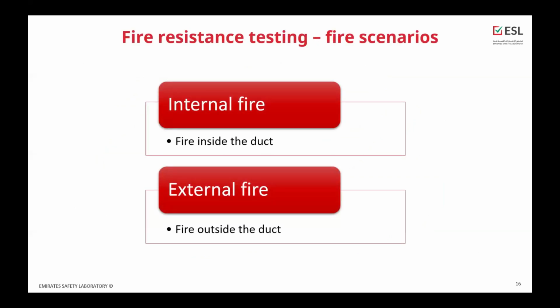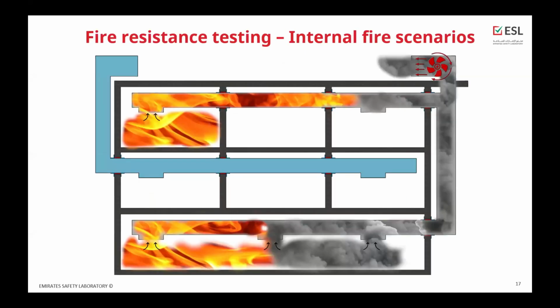During the test, we are doing fire resistance testing of the ducts under two scenarios: internal fire and external fire. Internal fire simulates the situation where the fire is pulled into the duct system. However, as you can see on this graph, the duct is also exposed from outside, so we have both external and internal fire. If we are talking about a multi-compartment duct, this fire can go through to the second compartment.